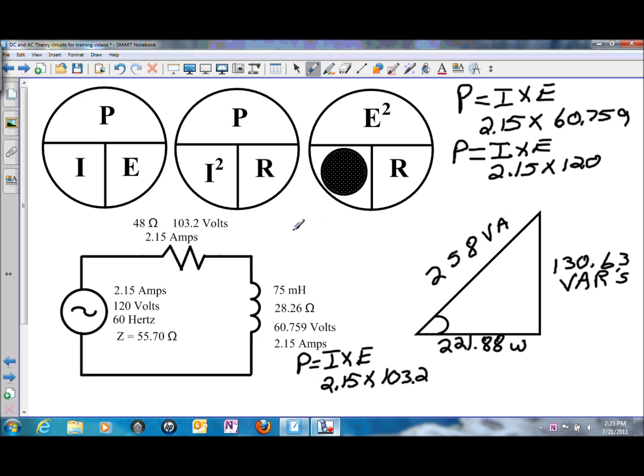Now we could take the values and apply them into Pythagoras theorem. So the volt amps would be the watts squared plus the VAR squared. If we took the 221.88 watts squared plus 130.63 VAR squared and the square root of that, the number comes up to be pretty much the same, 258 volt amps.